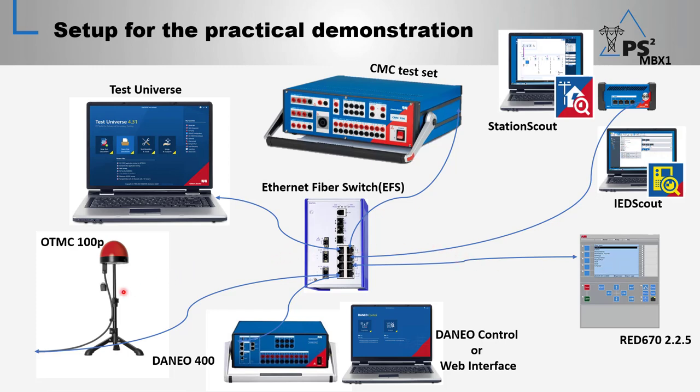And we have the OTMC100P, which is a PTP grandmaster clock connected to the Ethernet fiber switch, a managed switch from Hirschmann. It is also acting as a PTP transparent clock so that the test sets and the IED under test are synchronized to one common time source.